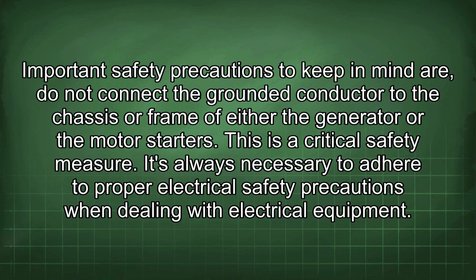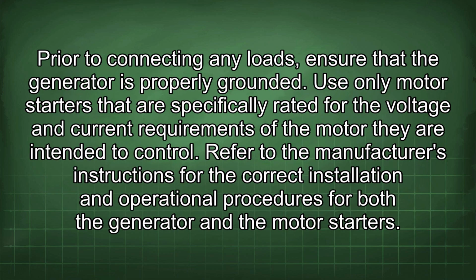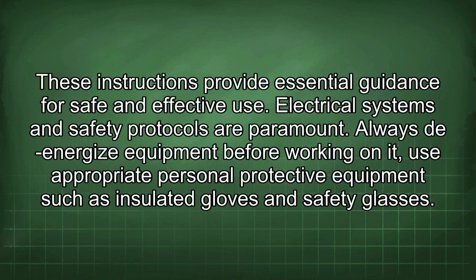Important safety precautions to keep in mind are: do not connect the grounded conductor to the chassis or frame of either the generator or the motor starters. This is a critical safety measure. It's always necessary to adhere to proper electrical safety precautions when dealing with electrical equipment. Prior to connecting any loads, ensure that the generator is properly grounded. Use only motor starters that are specifically rated for the voltage and current requirements of the motor they are intended to control. Refer to the manufacturer's instructions for the correct installation and operational procedures for both the generator and the motor starters. These instructions provide essential guidance for safe and effective use.